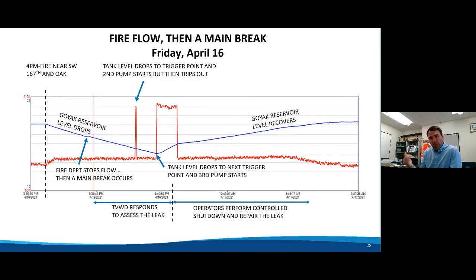And it dropped to a point where Scada had a setting to start another pump and said, okay, we've increased pumping rate a little bit. It wasn't quite enough. We're still dropping, so we're going to start a pump. And that's what you see here. But we had an issue in that pump station, and that pump tried to start and did not run very long and then tripped out. So we had a little bit of a fibrillation there, if you will, on the cardiac side. And the tank continued to drop.